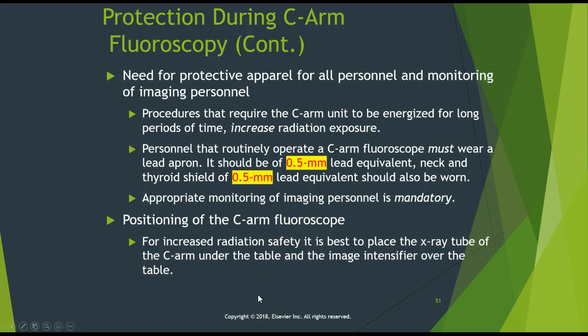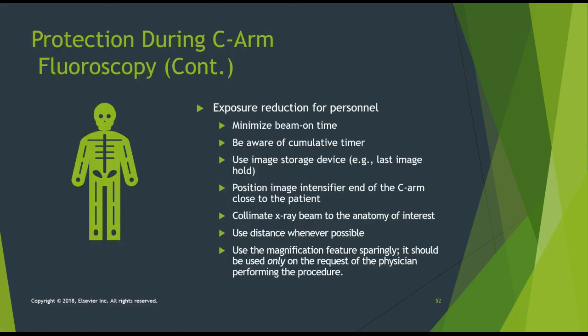For increased radiation safety, it is best to place the X-ray tube of the C-arm under the table and the image intensifier over the table. You also need to minimize beam on time. Be aware of the cumulative timer. Use the image storage device, for example, last image hold. Position the image intensifier end of the C-arm closest to the patient.